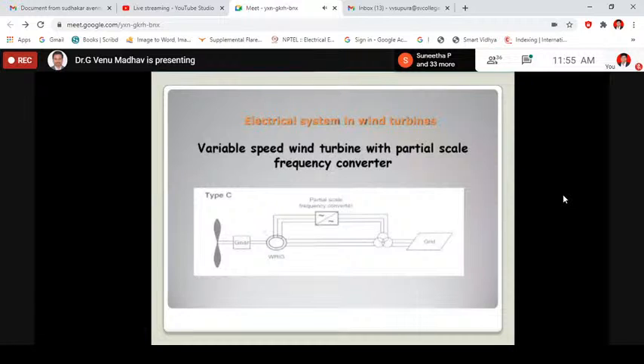The grid side converter controls the DC link power and the reactive power being injected to the grid, which is very, very important. In the previous comparison, only the grid frequency was connected - it's available, I cannot change to any other frequency and control it.